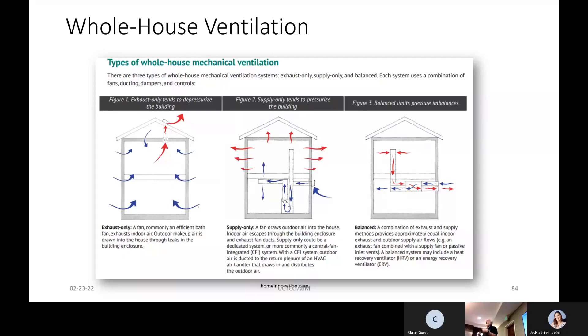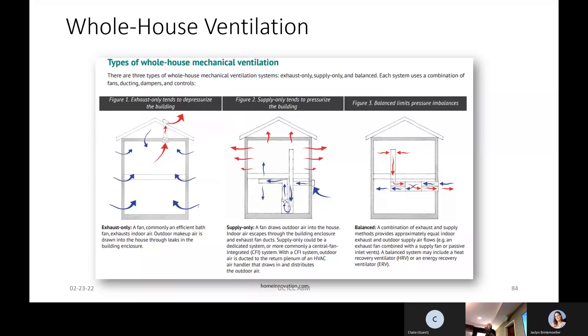What's the golden number — if you exhaust too much air, what's the point the house can't leak enough? There's a number that's been arrived at and it's in the code. If you have a fan moving more than 400 CFM, you have to have a makeup air provision. For a smaller fan, it will make up itself by leakage. It's really hard to get a house down super tight — there are so many little places for air to enter, even the weep holes in windows.